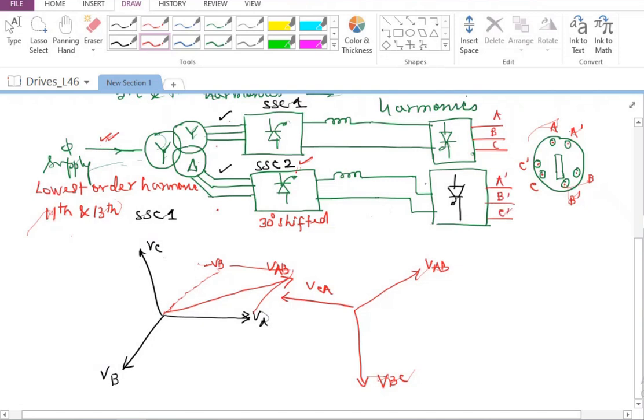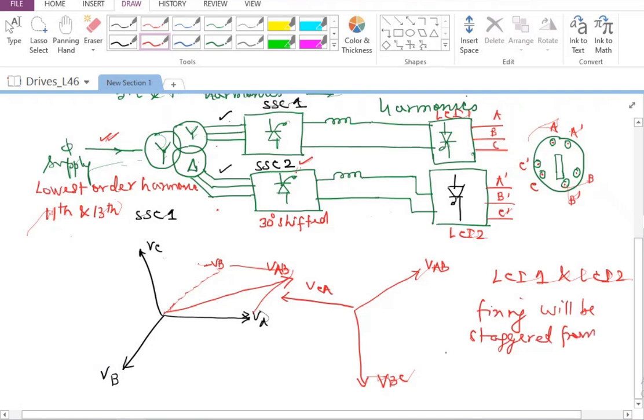And I'm going to again fire these two. That is, if I say this as LCI1 and this as LCI2, LCI1 and LCI2 firing will be staggered from each other by 30 degrees. So the 30-degree phase shift, what we see for A, B, C, I can simply connect this to the synchronous machine stator. Similarly, A dash, B dash, C dash will be connected to the second set of synchronous machine stator winding. So the rotor will be able to get the magnetic field corresponding to both sets of windings. So ultimately, the power input that goes to the synchronous machine will be twice whatever is the power input coming from one single converter.